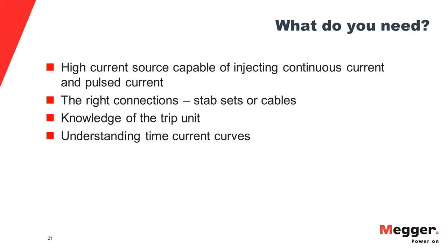You need to have a good knowledge of the trip unit. You need to be able to know how to operate the trip unit to set the right delays and the pickups required to do the test. You need to understand the time current curves to be able to validate the results that you get.